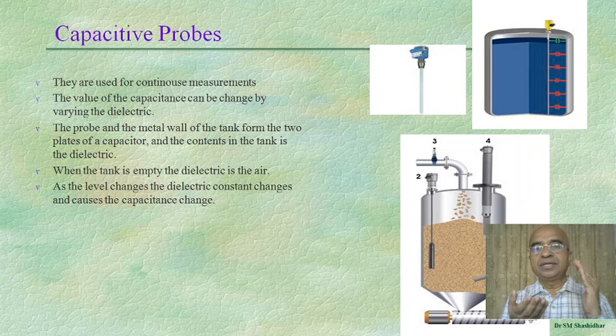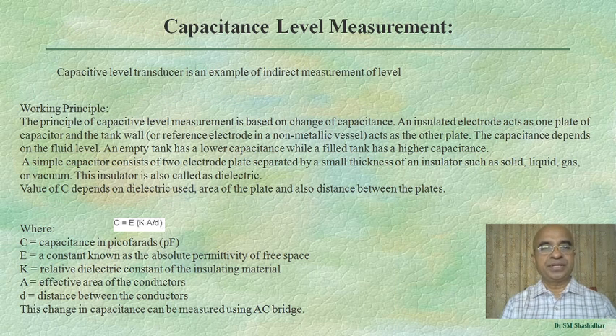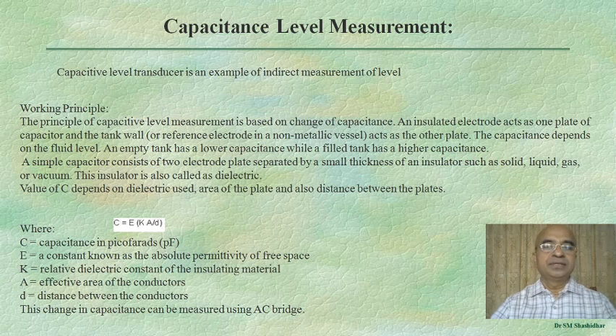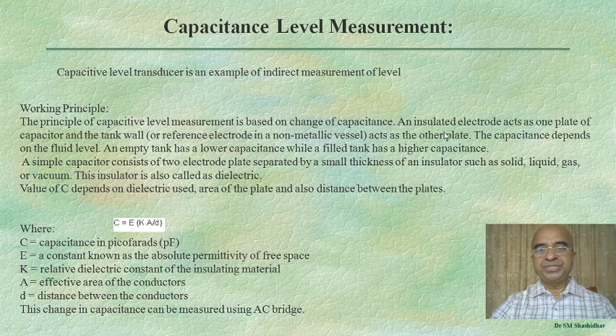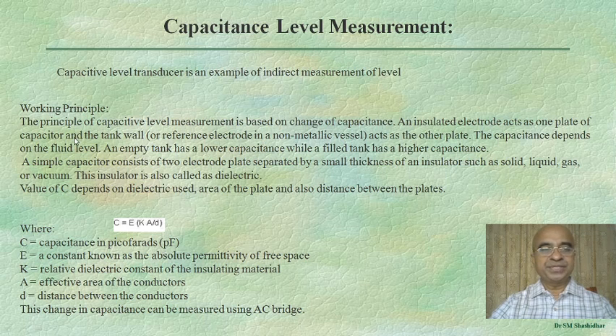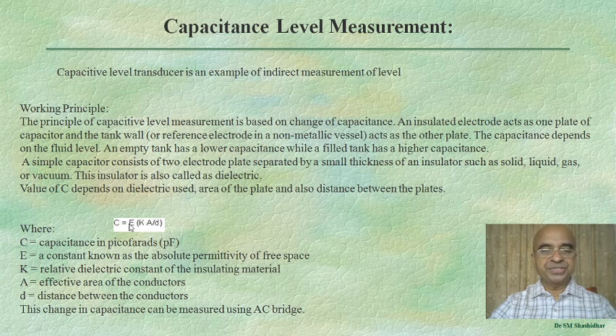We can map the value of the dielectric constant to the level of the liquid in the tank to obtain capacitance-based level measurements. This is an indirect method. The principle is based on change of capacitance: an insulated electrode acts as one plate and the tank wall as the other. An empty tank has a lower capacitance while a filled tank has a higher capacitance.